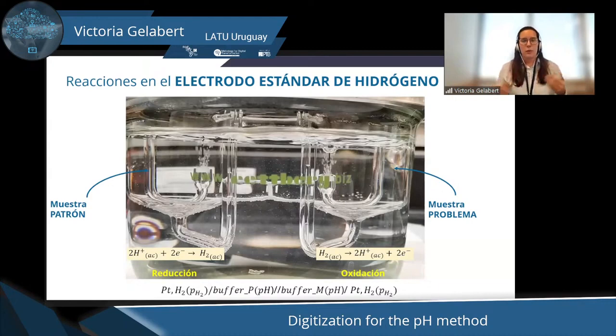This is an electrochemical reaction, and in other types of tests, you might have a rupture, you might have certain signals where you're measuring and they abruptly end, or you might have a change in color. However, that's not the case here. Here, you're going to have an electrochemical balance, which isn't immediate, specifically because of the volume. It's more or less 80 milliliters in each side. This might take an hour to 5 or 6 hours.